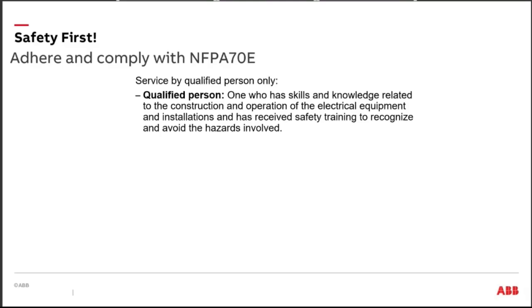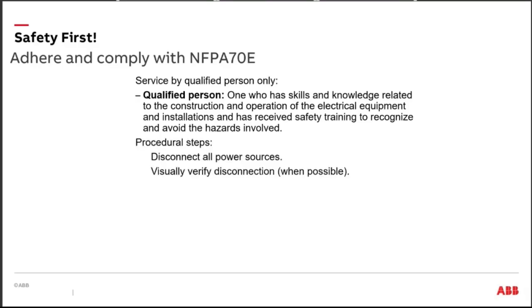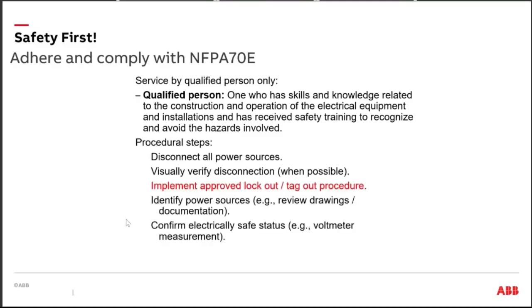So if you're a manager out there, if you're the person in charge and you're taking care of getting people to the job site, make sure that you do have that qualified person going out to that job site. It's important. When we start talking about a variable frequency drive, we want to disconnect all our power sources. You've got to really look at that. It's not just the three-phase mains or the single-phase 230 volts that's coming into it. We might be switching 120 volt on a drive fail relay somewhere, or you might have 120 volt on a drive run relay. So even though you've got your mains disconnect open, you might have the fuses pulled, you might still have voltage in that cabinet from a secondary source.